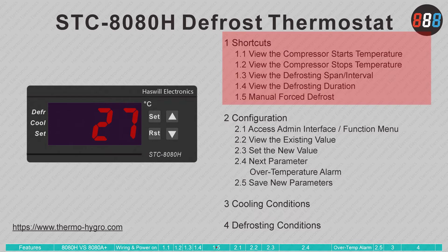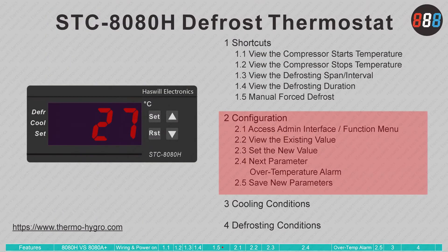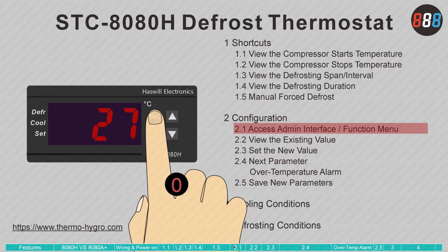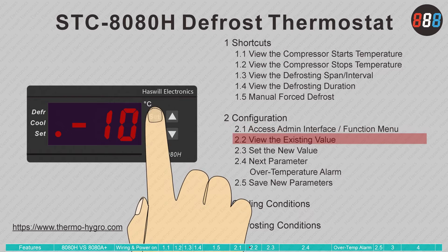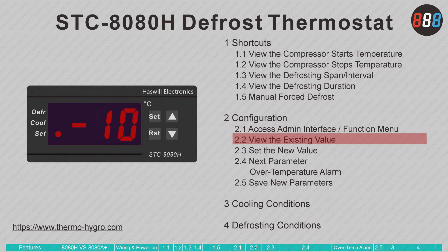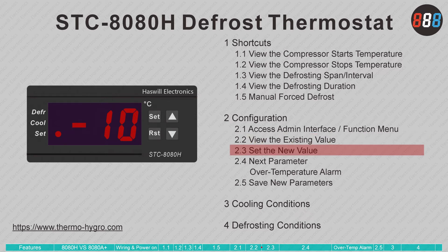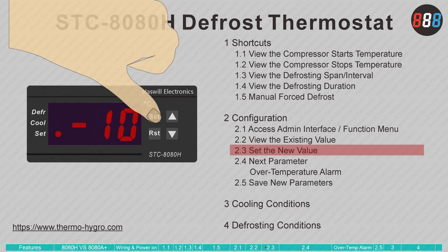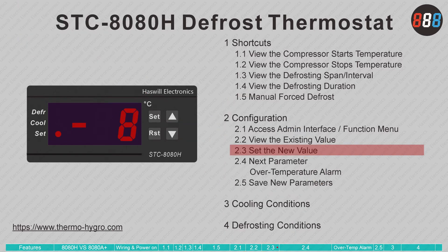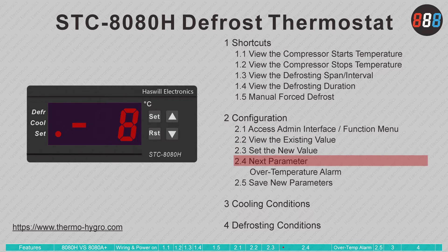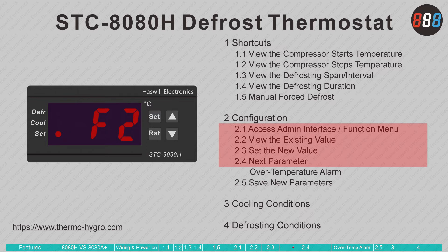Those are how to view existing values. Now, here is how to configure the STC-8080H. Step 1: press and hold the Set key for three seconds — you will see F1, meaning you are in the configuration interface. Step 2: press the Set key once to view the existing value, currently minus 10 degrees. Step 3: press and hold the Set button and, without releasing, press the Up button to change the value — for example, to minus 8 degrees. Step 4: switch to the next code by pressing the arrow button.